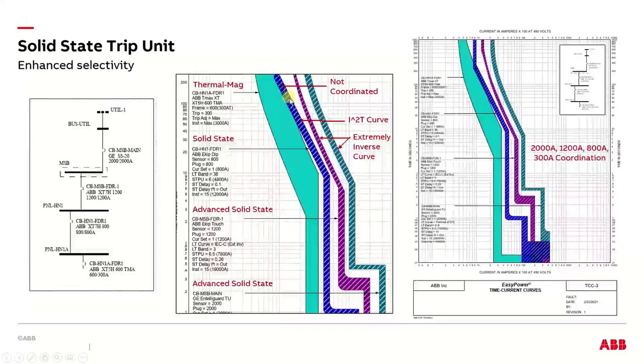But if you notice, this is a straight line, but the purple and the green are slightly curved. So what these curves are, this was set to extremely inverse, and this breaker doesn't have that functionality. So in this specific case, you would have to upgrade this normal solid state trip to a solid state trip that you could adjust the curve type. Because if you could adjust this curve and match extremely inverse, it would turn a little bit and be perfect and perfectly fit into that area.